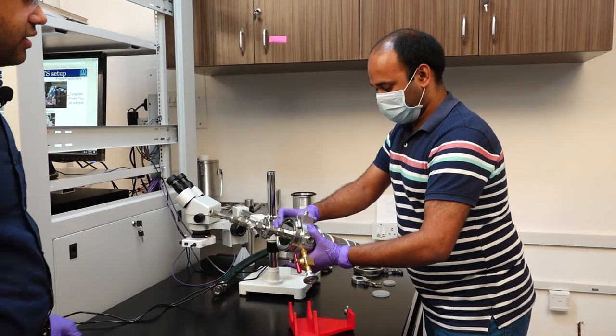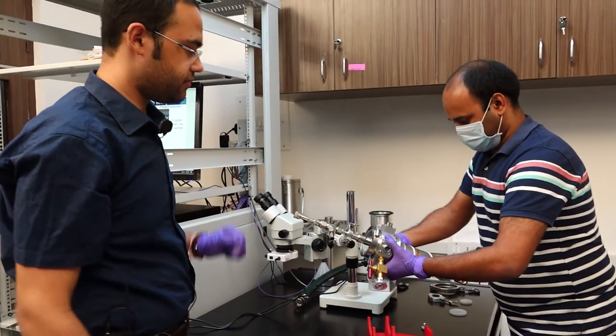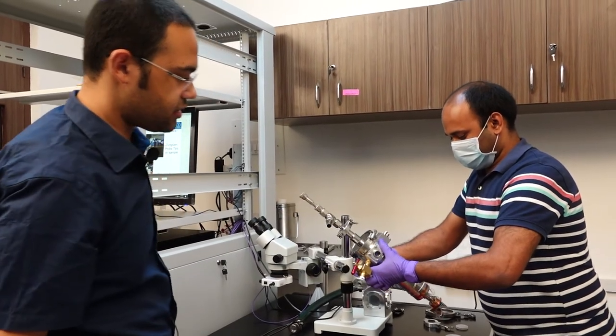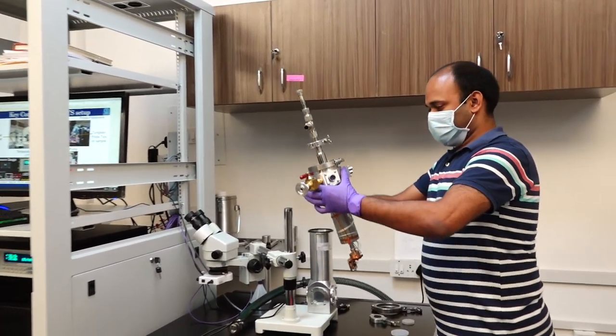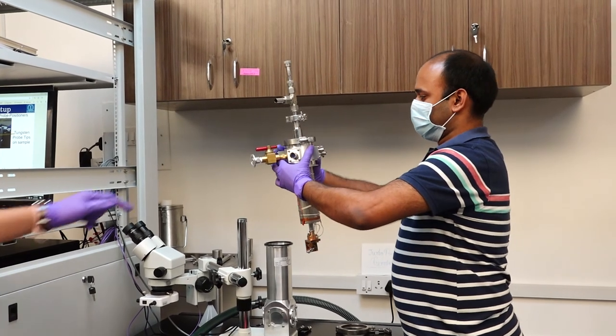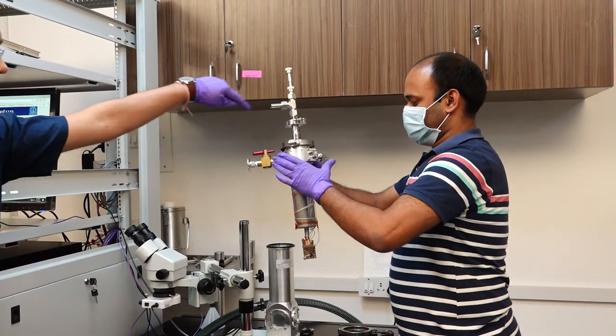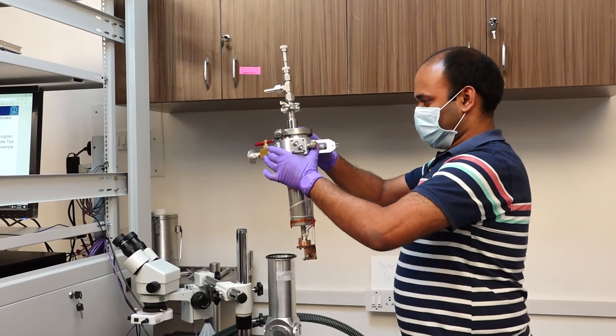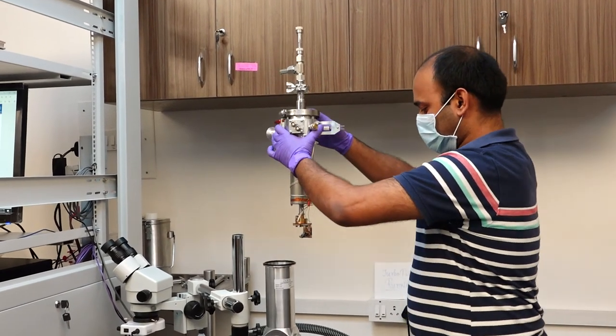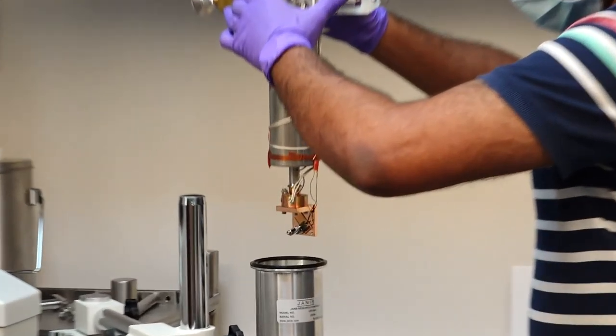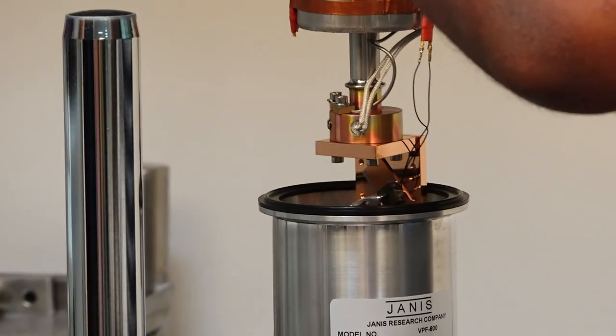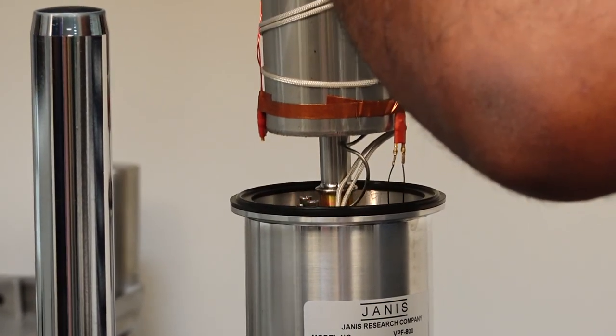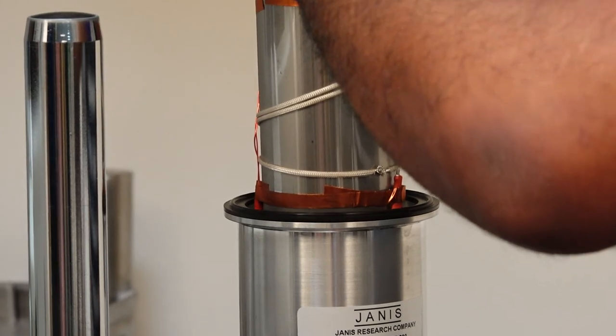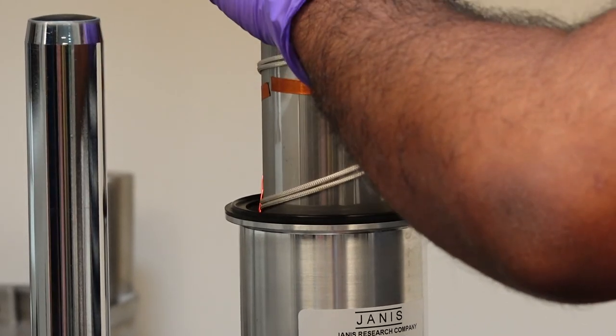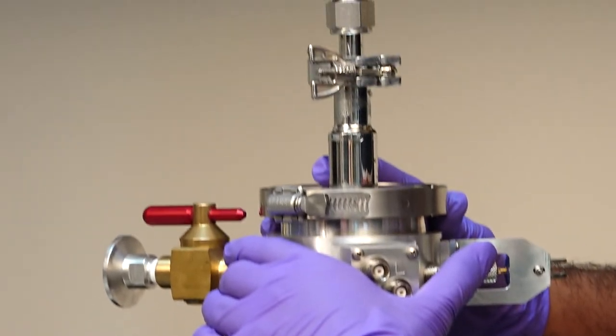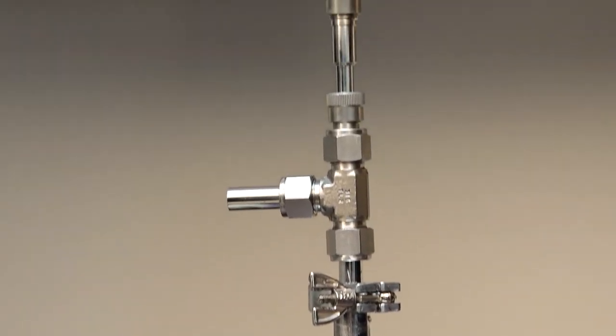One must ensure that while loading, we should not touch the wired regions because there are delicate connections which might be hampered. So as you can see, we have to hold this outer rim. Most importantly, while loading in, we must ensure that this L-shaped sample stage does not hit the inner cylindrical walls, because if it hits the inner walls, then your probe might go out of the contact pads.